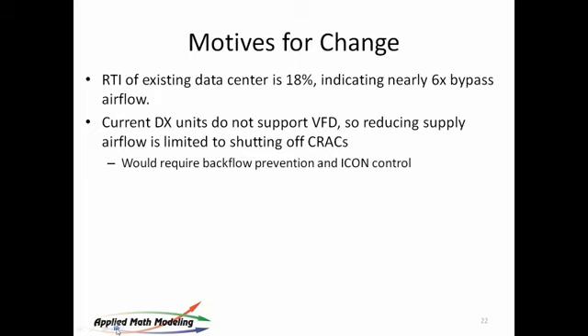Now these are DX units and they don't support VFDs. So reducing the supply airflow is really limited to shutting them off. And when you shut off DX units, you need to be sensitive to the fact that there may be backflow coming back up through those units. So you may want to put backflow prevention louvers under that. And you'll no doubt want to connect them together so that if one goes down, the other one comes back up. You can do that using the icon control. There are controllers now on these CRAC units that allow you to wire them together, network them together, so that the failure of one would spark the startup of another.